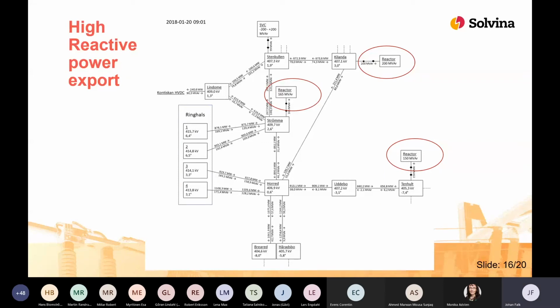And I also want to say on this date, it's not shown in this visualization, but later during the day, when the loading increases even more, the reactors are disconnected. And we can say due to the high loading during this period, Ringhals still had to produce a high value of reactive power. This might indicate that the Ringhals reactive power production capacity is quite needed during this high load situation. We have seen it in other instances as well.